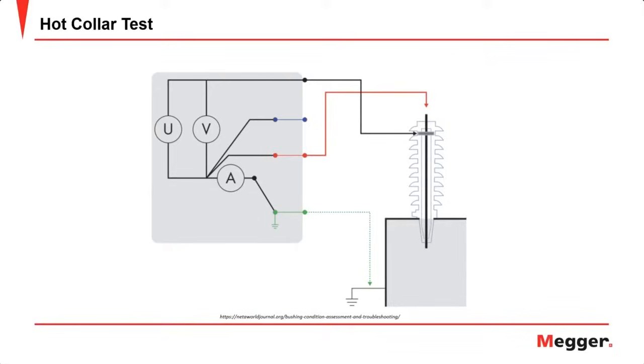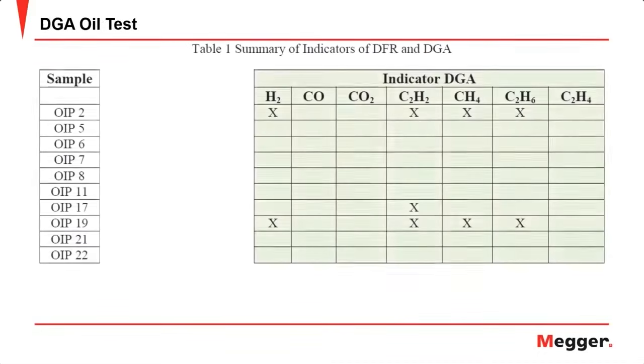And then finally, on the OIP bushings, we do have the ability to take an oil sample and then send that to a lab for DGA analysis, where we look for hydrogen, acetylene, methane, ethane, and ethylene.